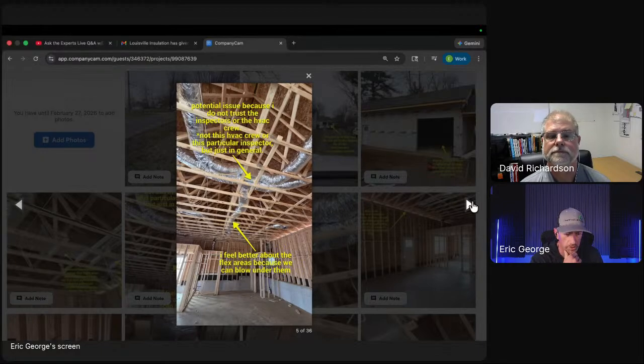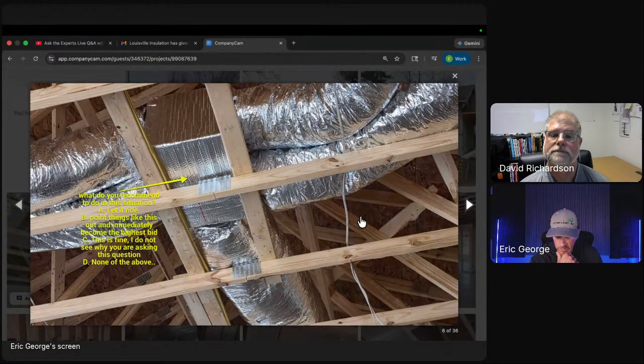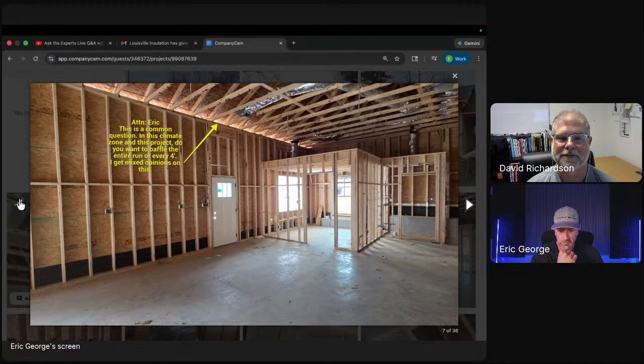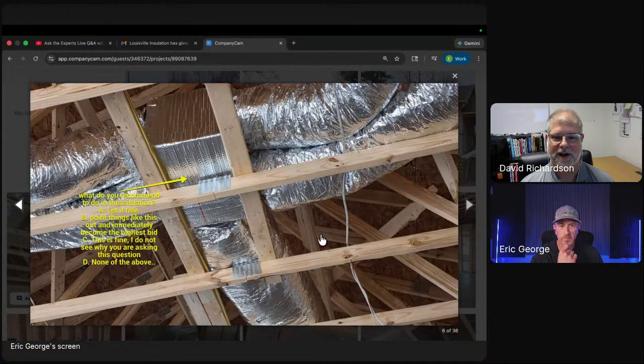Feel better about the flex under here. So what do you recommend to do in this situation? Let it ride, point things like this out, and immediately become the highest bid. This is fine. I don't see why you're asking this question. None of the above. The first thing I would want to know is, where's the design for it? Is there a design? That's where the rubber is going to meet the road on this. How did you get your design? If they're using some type of rule of thumb, like 0.10, or this size flex duct gives me so much air, red flag. In general, I see this Reflectix stuff used all the time. This looks like it's actually the R4 and not the R8 bubble wrap.